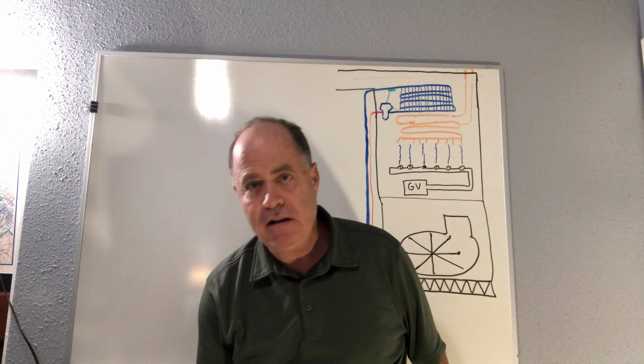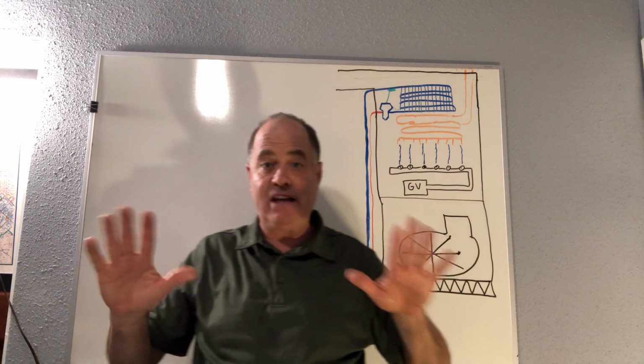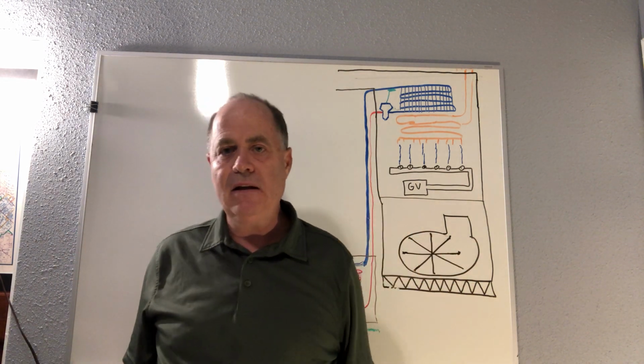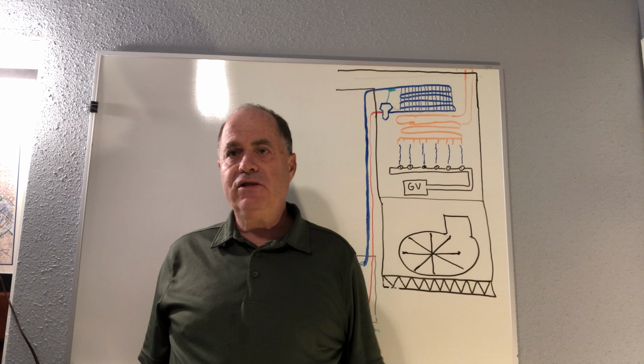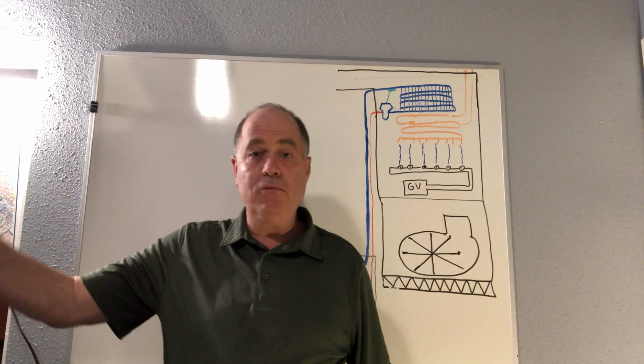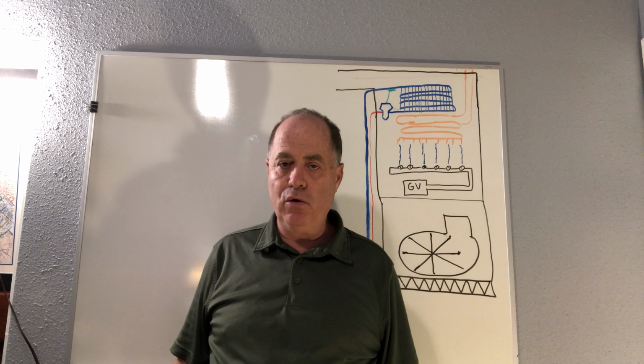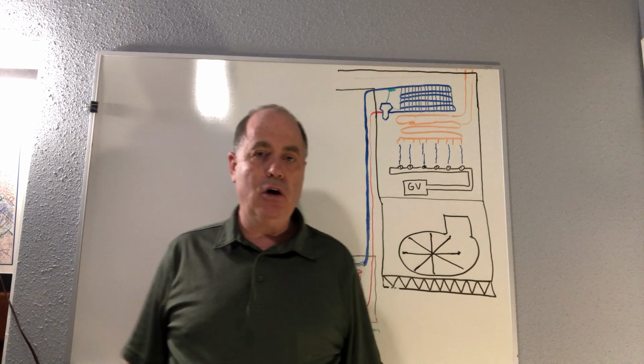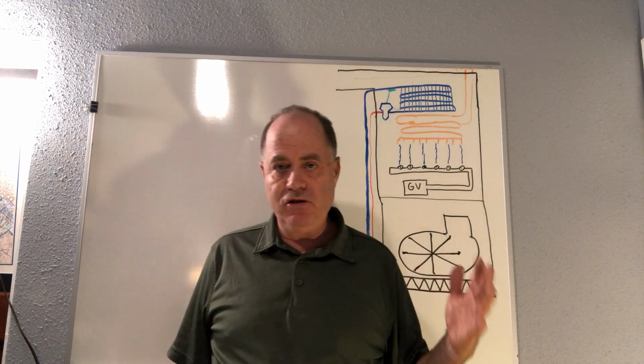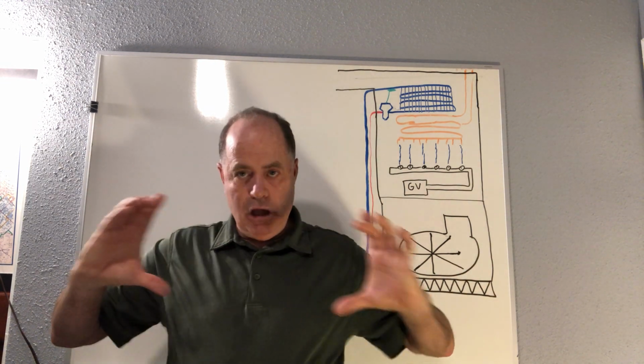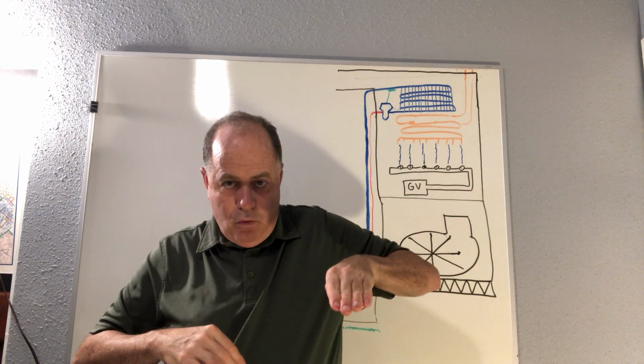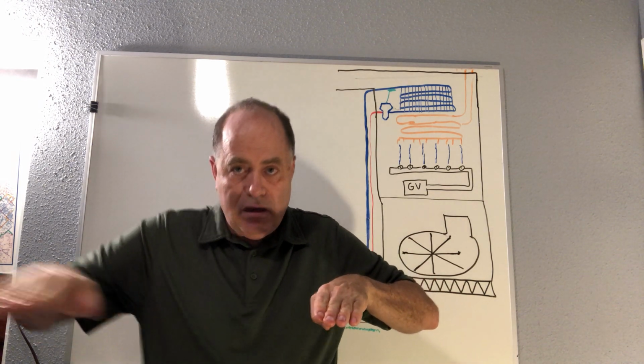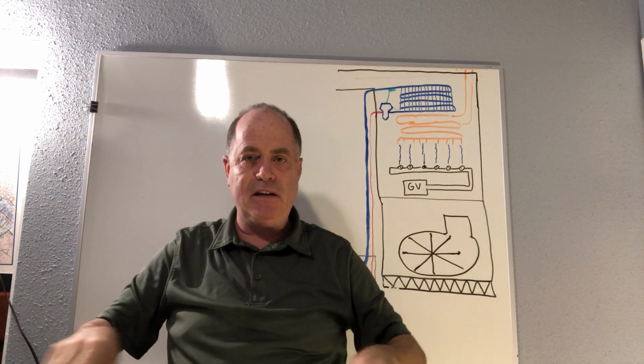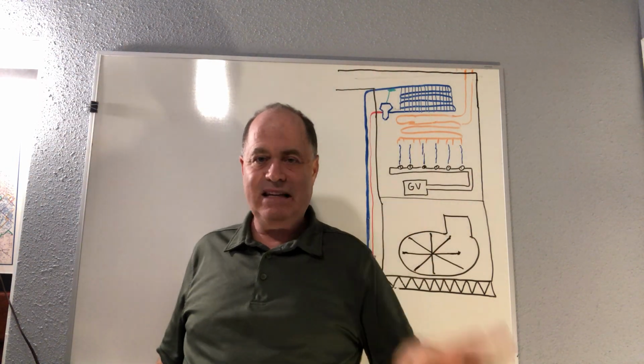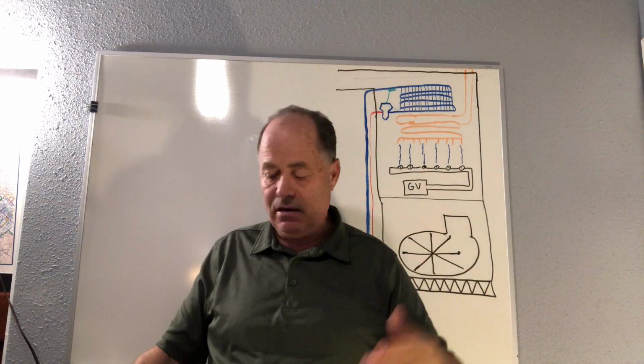And sometimes you still have little under the counter refrigerators that have that static condenser with no condenser fan. So you do need to have air clearance so that you can have air movement around it to dissipate the heat and lower your head pressure. Generally speaking, though, most modern refrigerator freezer combos in your house have a grill down low, and they take the air in one side and blow it through the condenser and have the air come out the bottom side, and then people make them seamless right underneath the cabinets and build them in so they're nice and tidy and more appealing to some people.